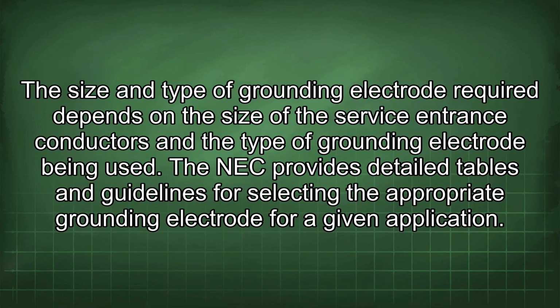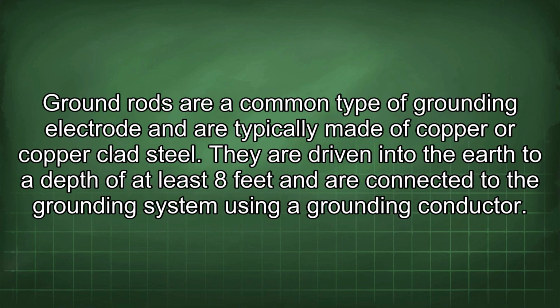The size and type of grounding electrode required depends on the size of the service entrance conductors and the type of grounding electrode being used. The NEC provides detailed tables and guidelines for selecting the appropriate grounding electrode for a given application. Ground rods are a common type of grounding electrode and are typically made of copper or copper-clad steel. They are driven into the earth to a depth of at least 8 feet and are connected to the grounding system using a grounding conductor.